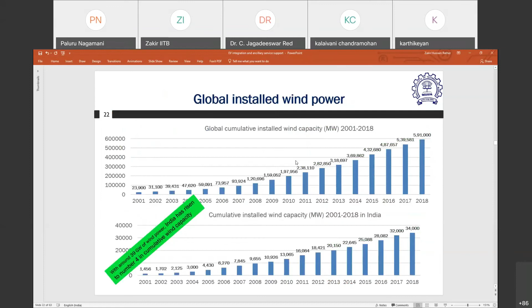I think I'll skip this. This is understood. We are increasing the renewables, but all I want to highlight is that because of the displacement of conventional generators, we are losing the inertia in the grid, which we have been discussing earlier. Inertia is what helps frequency stability in the beginning, and because of this diminishing inertia, for the same disturbance we will experience a larger frequency nadir, meaning worst-case frequency, which means potential load shedding and, in the worst case, grid blackout. So we need to look at how this diminishing inertia will be countermeasured.